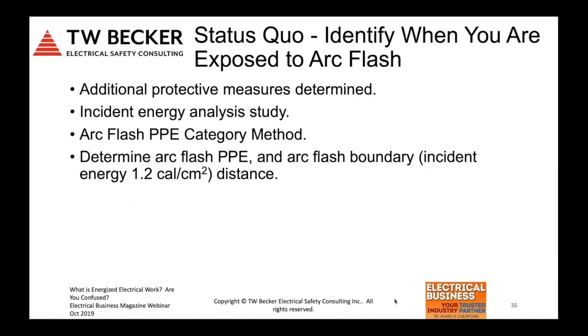Additional protective measures are determined, as I indicated. Incident energy analysis study or the arc flash PPE category method can be used to determine arc flash PPE and the arc flash boundary. And then the worker needs to understand what the working distance is and maintain that distance to their face and torso when they're doing the work task that can expose them to an arc flash. And again, the arc flash boundary is calculated or determined where the incident energy would be 1.2 calories per centimeter squared. And if you're outside the arc flash boundary, we don't need arc flash PPE to be worn.